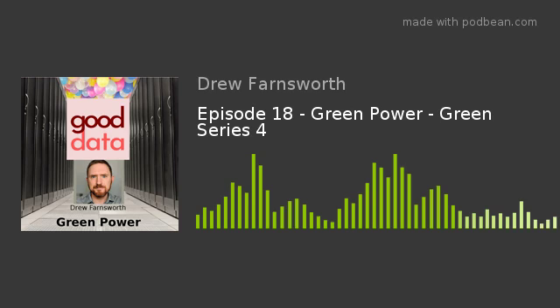And we're back. So we've talked about the electrical distribution, the UPS, but what about generation? There are always at least two different sources of generation in a data center. There is the utility, and then there's the backup generation. Most of the time, very much most of the time, that backup generation is a diesel generator. And that's because they're fairly inexpensive. You can get diesel fuel and refill it in case there's some kind of a problem. You can always run them. You can get the fuel anywhere. There's somewhat less maintenance on a diesel generator. They're just very reliable and well understood pieces of equipment.